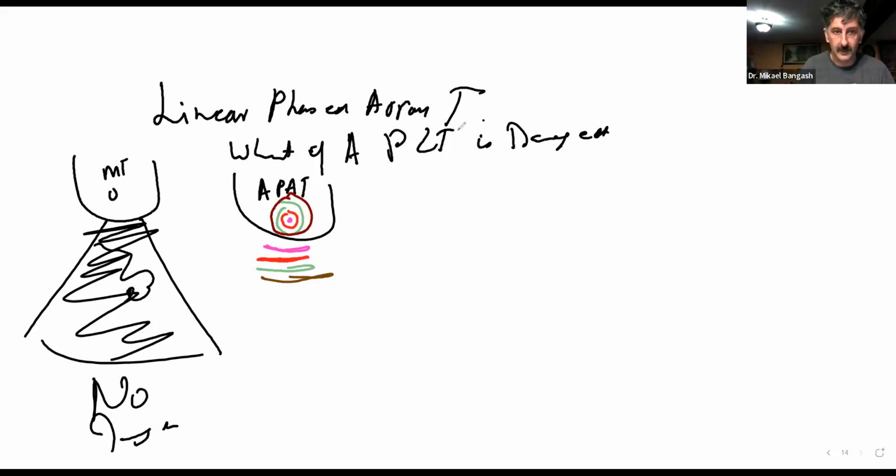And if, for instance, we damage this green one here, we will have a black area, a hypoechoic area across the area which was being focused by this PZT, because that was damaged.